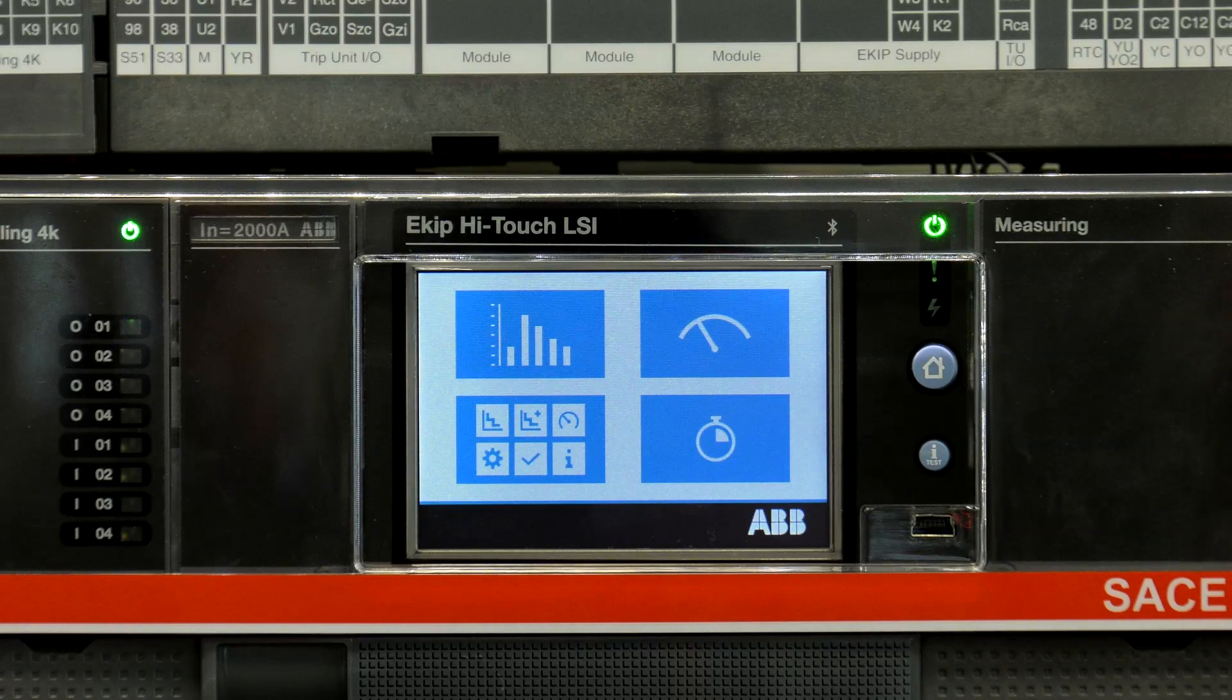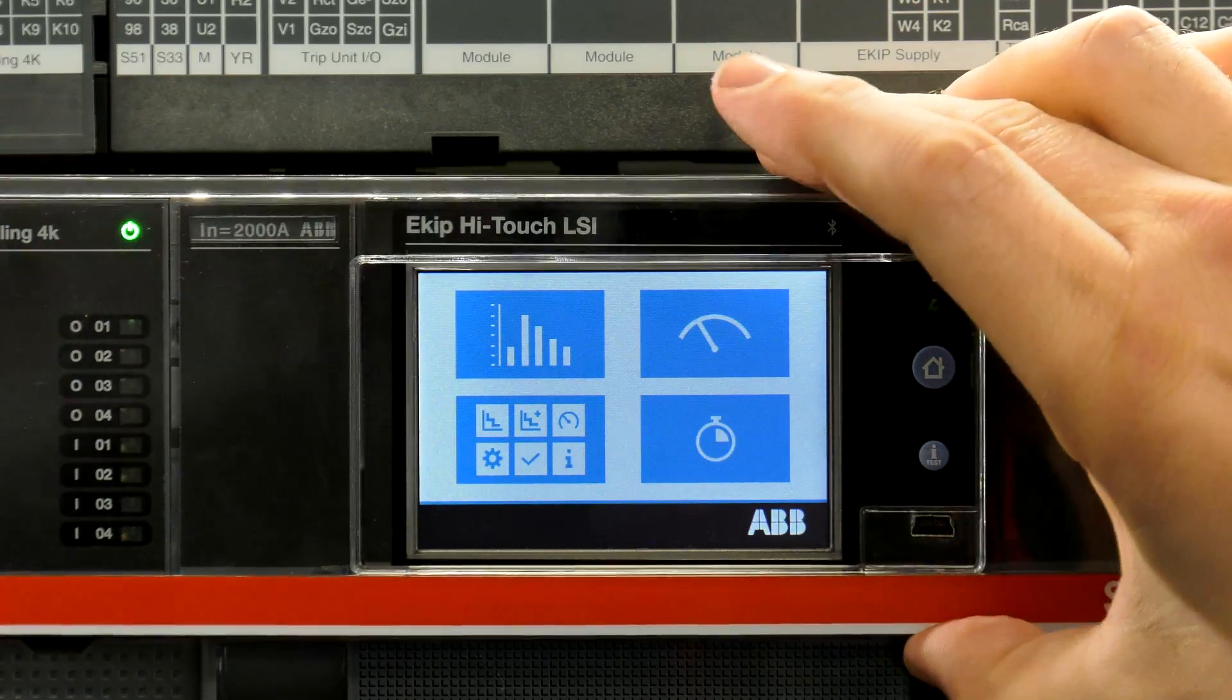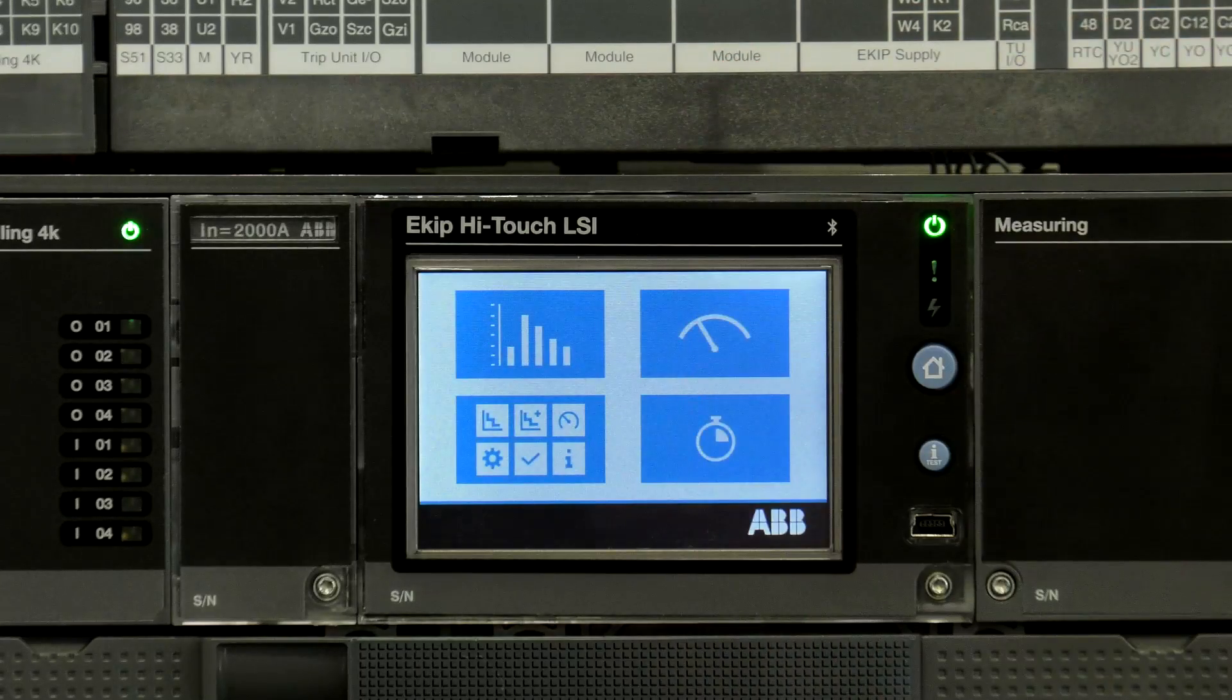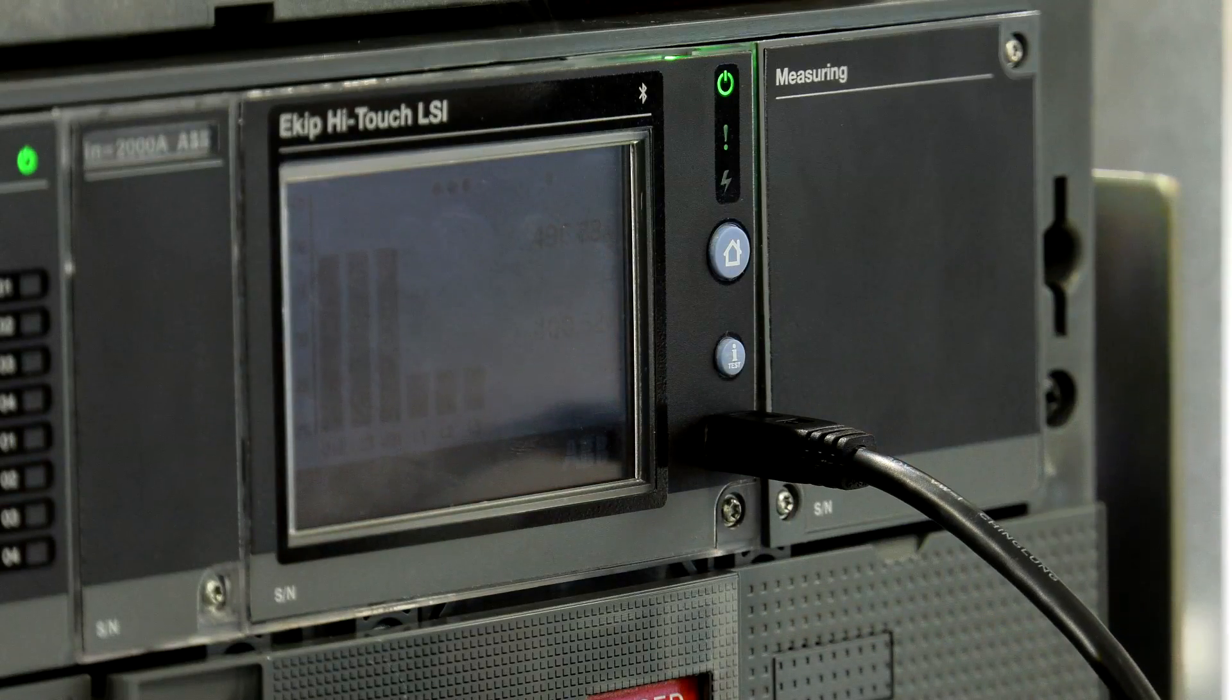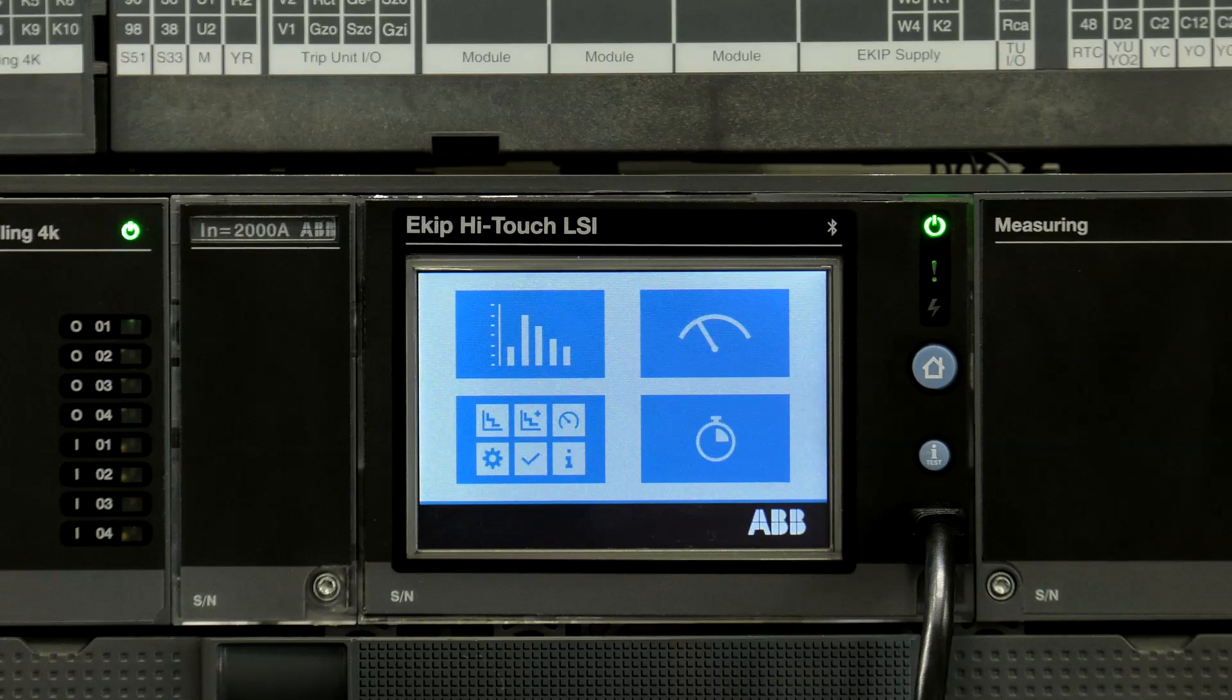First, remove the front cover from the trip unit. Then insert the micro-USB cable from the programming unit into the micro-USB port on the front of the circuit breaker.